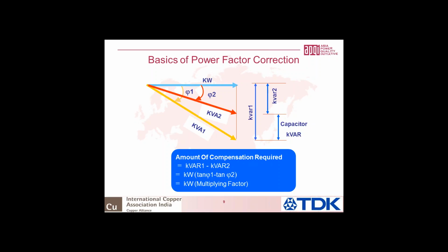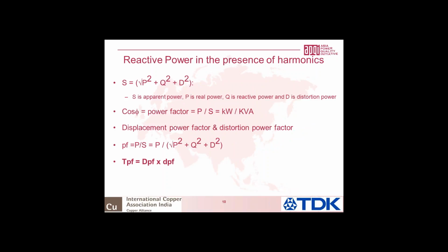Now let's look at what happens in the presence of harmonics. The previous equation we saw, where apparent power is equal to the square root of real power square plus reactive power square, gets modified here. As you would see on the screen, I've written S is equal to root of P square plus Q square plus D square. And the D is the new introduction because of the presence of harmonics, and it's called the distortion power. So we not only have to contend with apparent power, real power, and reactive power, we now have to be concerned about distortion power.